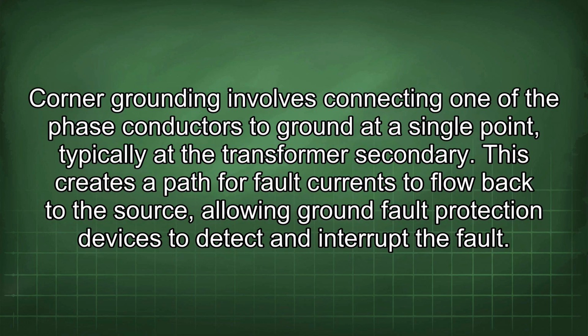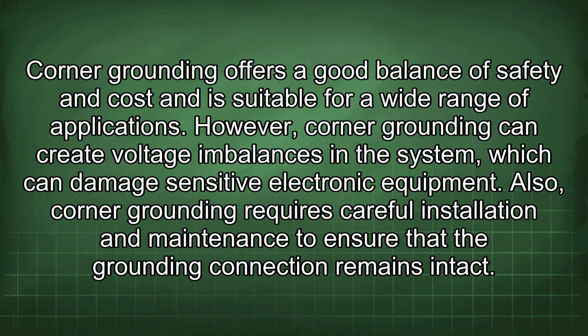Corner grounding involves connecting one of the phase conductors to ground at a single point, typically at the transformer secondary. This creates a path for fault currents to flow back to the source, allowing ground fault protection devices to detect and interrupt the fault. Corner grounding offers a good balance of safety and cost and is suitable for a wide range of applications. However, corner grounding can create voltage imbalances in the system which can damage sensitive electronic equipment. Also, corner grounding requires careful installation and maintenance to ensure that the grounding connection remains intact.